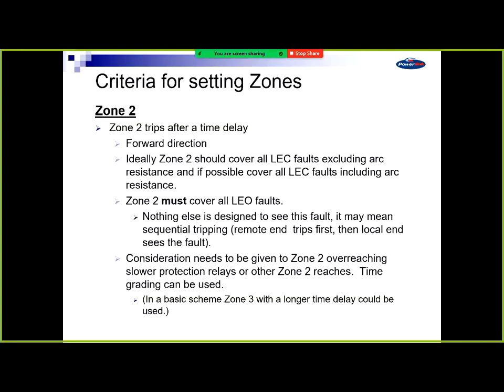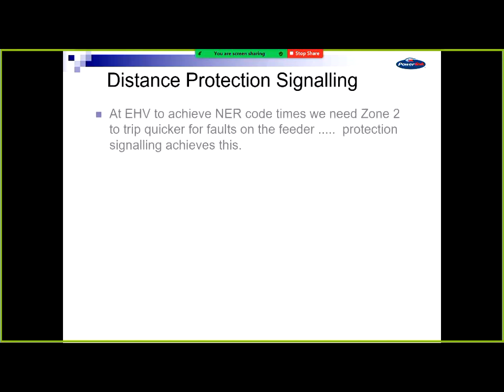When you're also doing zone 2, you have to consider, do I overreach onto other protection? And what are the consequences of that? So in our network where we've got a lot of big feeders, not often we have that zone 2 overreaching problem. It's only when we've got short feeders that remote feeders may see onto those remote zone 2s. If they're too short, we've got duplicate current diff. So to get a spurious trip of a zone 2 overreach on our network, we've actually got to have failure of 2 lots of communications or a relay and a communications failed. If we actually had 2 relays fail, they've got to take the planned item out of service. So it's not such a big issue for us, but it is a concern that you may have in some areas.